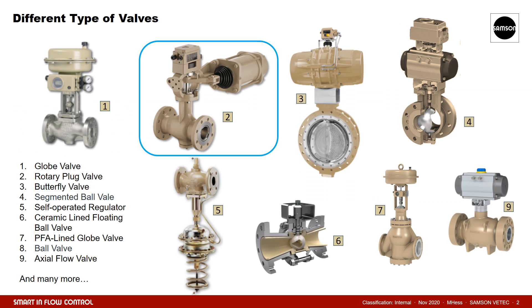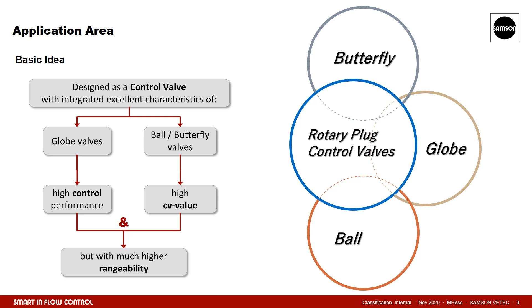The invention of the rotary plug valve goes back to the 1970s. As already mentioned, every valve type has its pros and cons. The globe valve, for example, is well accepted for excellent control behavior, whereas butterfly and especially ball valves perform best in the area of high CV values. Rotary plug valves combine the best of both worlds — excellent control behavior and, due to an outstanding rangeability, the ability not only to control high throughputs like ball and butterfly valves, but also smaller flows.